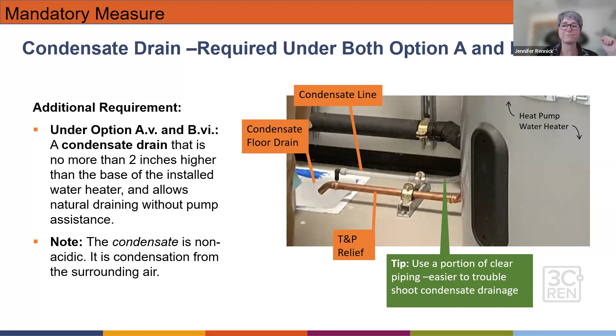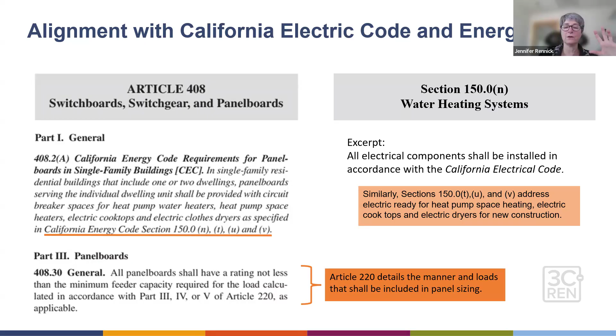And so in my case, I found that space. I'm going to demo an existing closet and make a new closet for it. But I could take that condensate line and put it right into this area where we're draining for my washing machine. And so that's a legitimate way to do it. But you need to think it through. And then there's a greater alignment with the electric code and the energy code for those requirements when you're doing the electrification, whether it's remodel or new construction. You still need to have all your electrical work comply with Article 220 and size your loads and make sure that your electric panel meets those loads.